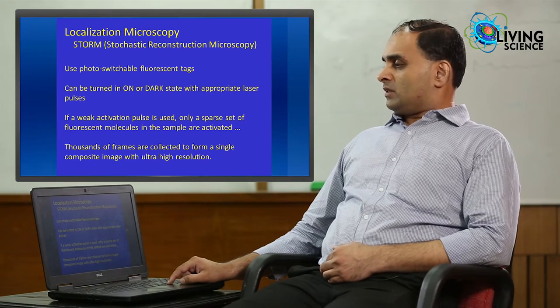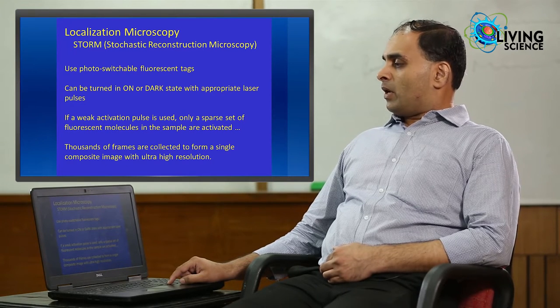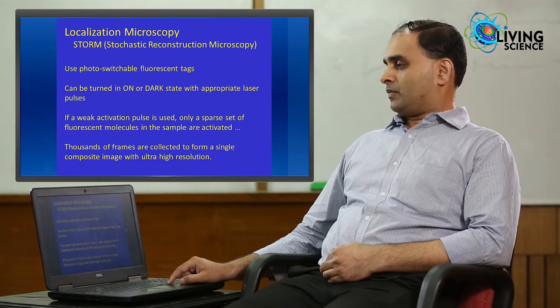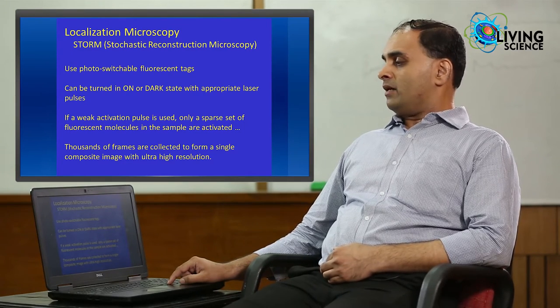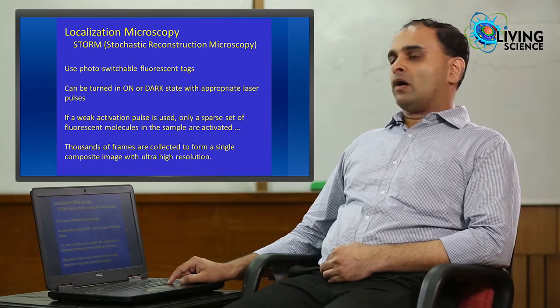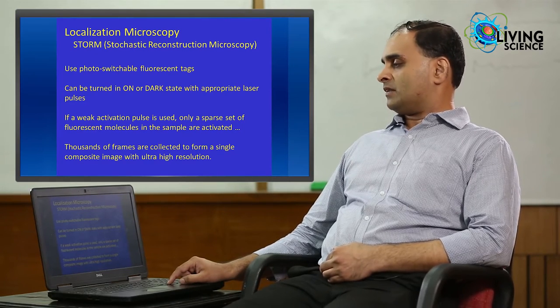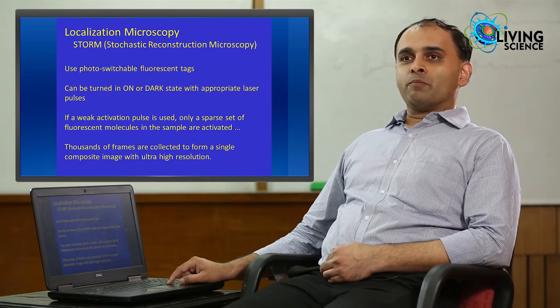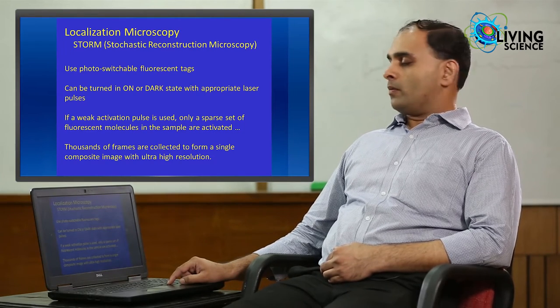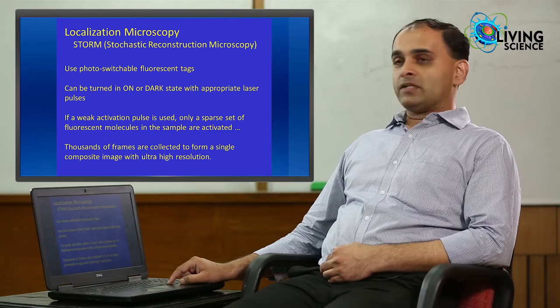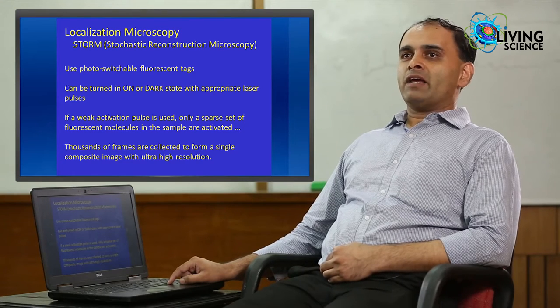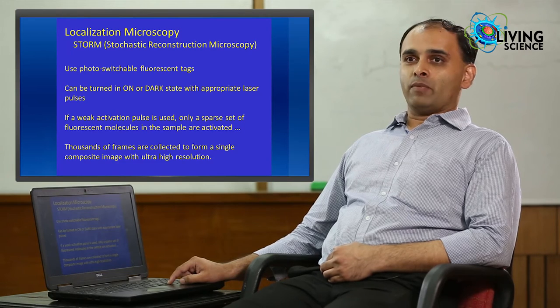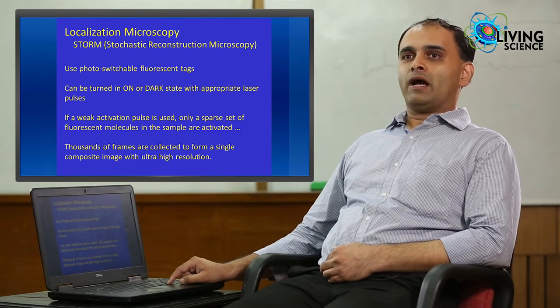To do this in a microscope, particularly you need photoswitchable fluorescent dyes or tags. They have special property that you can turn them on or dark state in on or dark state with appropriate laser pulses. Another trick that is employed in this type of microscope is that a weak activation pulse is used. So, that in any given frame only a sparse set of fluorescent molecules in the sample which are separated far apart are actually activated.